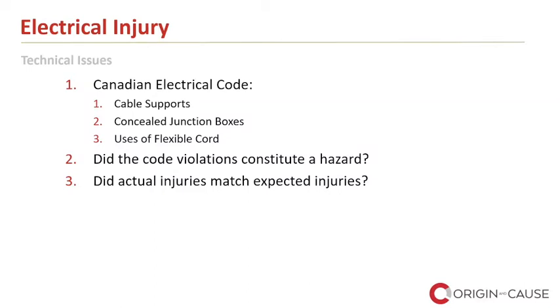The flexible cord issue, of course, was the biggest one. But the fact that the junction box was concealed meant that a casual observer wouldn't necessarily know there was power to the cabinet. The flexible cord violation did violate a rule that says no flexible cord may have exposed energized elements if one end is connected to power.